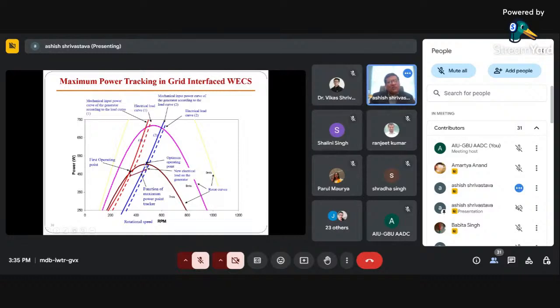Now we need to move towards the peak area of this, that is called the optimum operating point or the maximum power point tracking. So how can this be done? This can be done by adjusting your electrical load on the generator. That way we can shift this operating point towards the optimum operating point at a particular wind speed. If it is 7 meter per second, we should move towards here. If it is 8 meter per second, we have to move towards the peak point of this. This is how we need to adjust, and that can be done with your control scheme, so that the electrical load at the generator should be decided so that you can always extract the maximum power which you can extract from the wind energy.